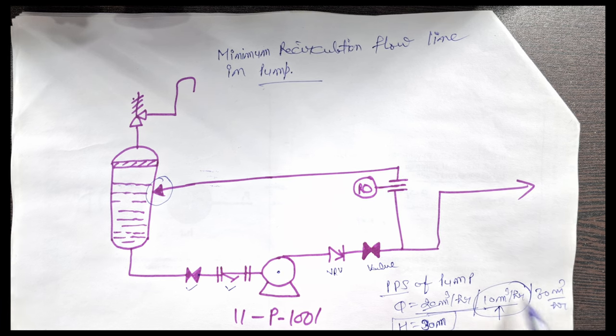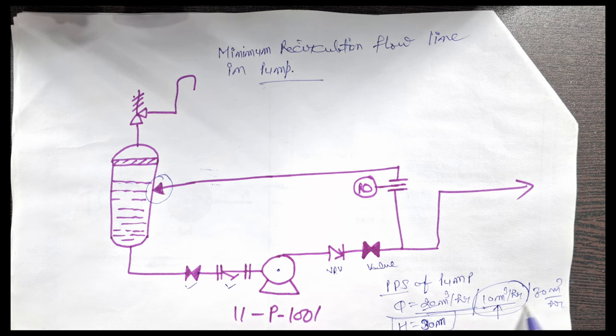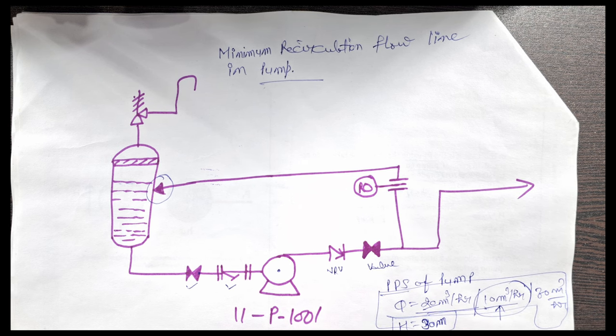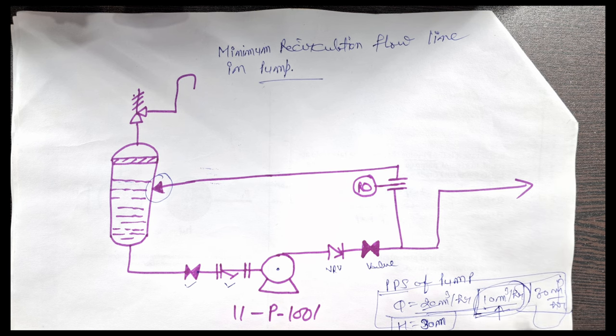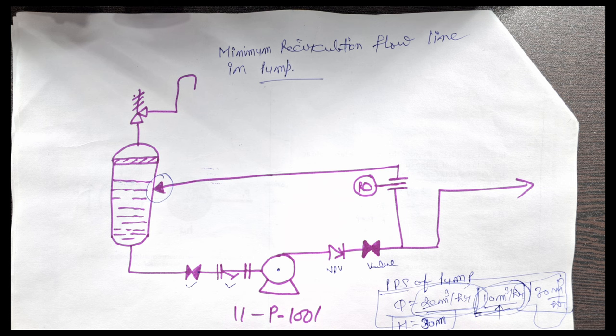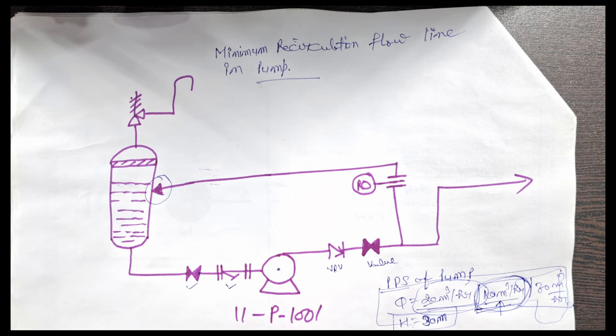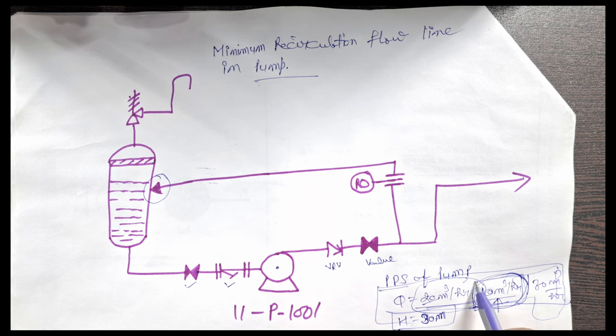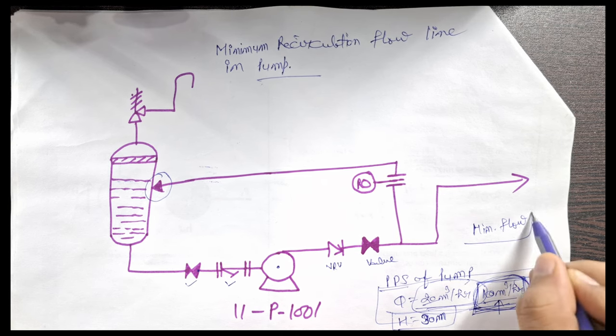Now the question is: what will happen if your pump goes below 10 cubic meters per hour? Simply, your pump could be damaged — the pump internal parts could be damaged — because it is designed within this range. When you look at the pump curve, the vendor provides a range from minimum flow to maximum flow, including the normal flow. If you go below the minimum flow point, the pump internals could be damaged.